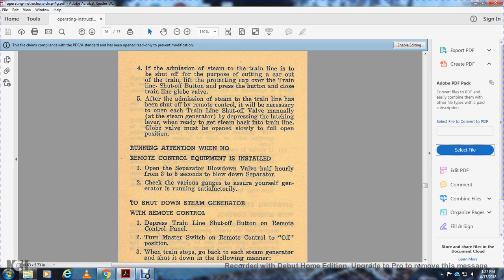Attention when no remote control equipment is installed. Open the separator blow down valve half hourly with a 3 to 5 second blow down of the separator with the various gauges to ensure that the steam generator is running satisfactorily.